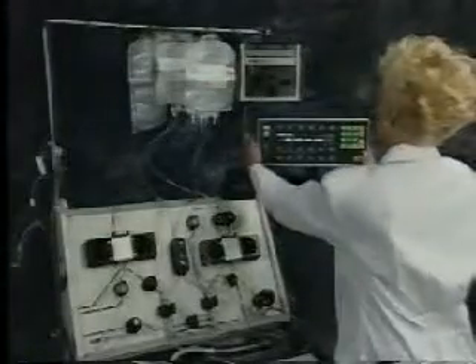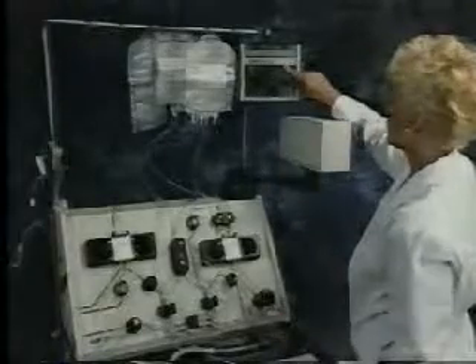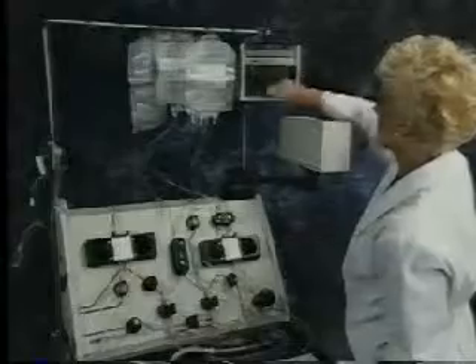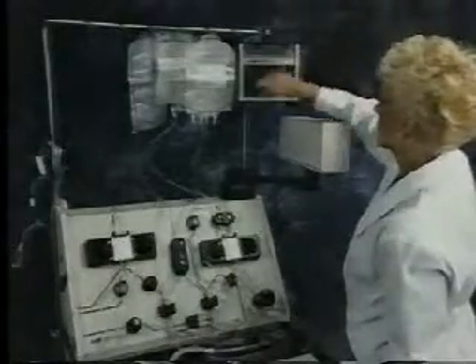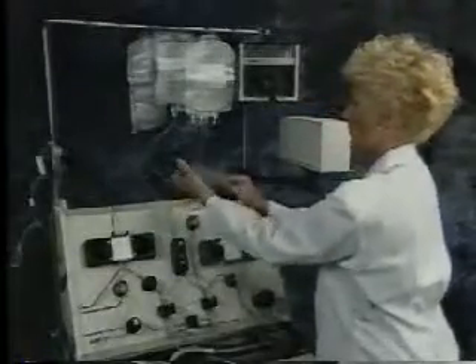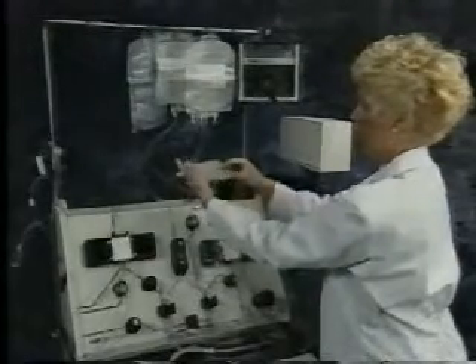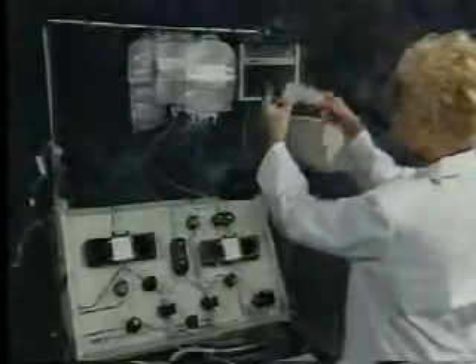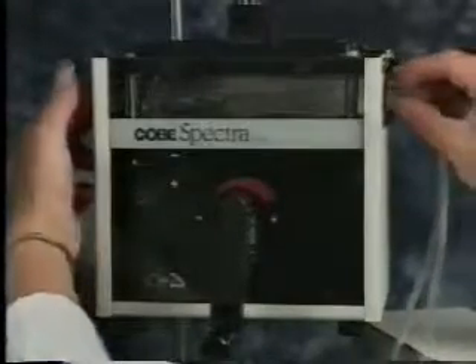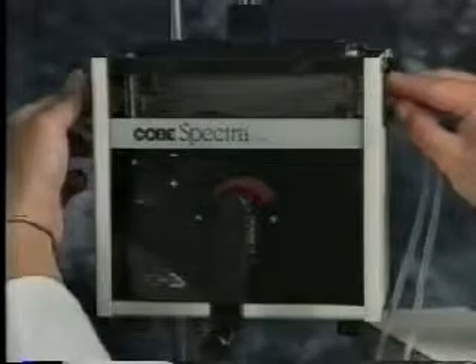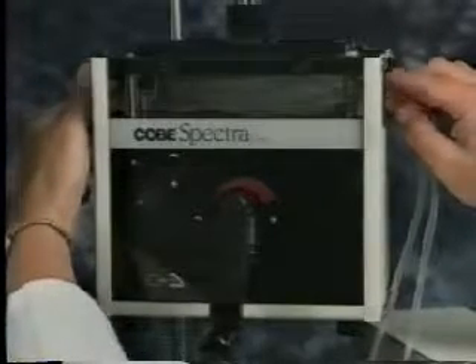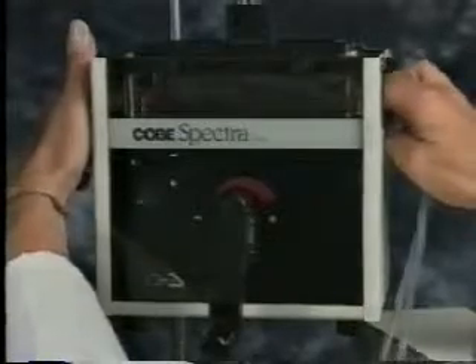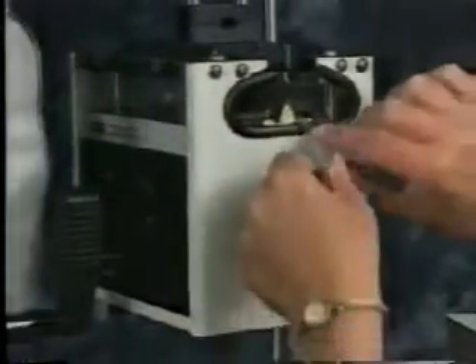Next, we need to load the return flow controller. Place the return flow controller into the load position by turning the hand crank counterclockwise to the load position where it will stop. The single needle bag is symmetrical and may be loaded with either side up. Fold the bag in half lengthwise and insert the bag into the right side of the return flow controller. Grasp the bag's load tab through the other side and place the bag's locator hole over the locator pin. Ensure the bag is lying flat on the plate. Place the bag's tubes on either side of the bag alignment block.